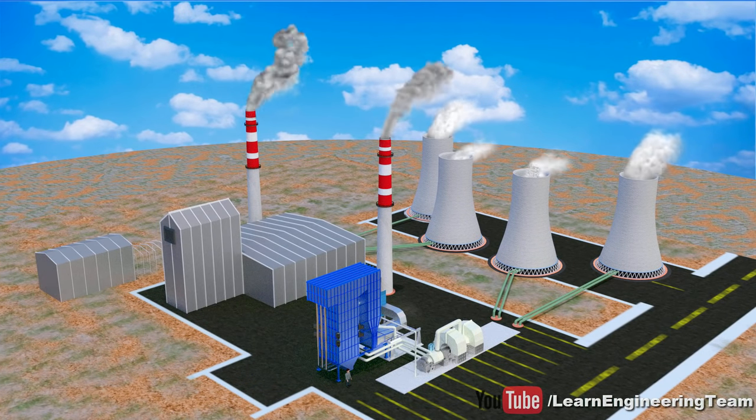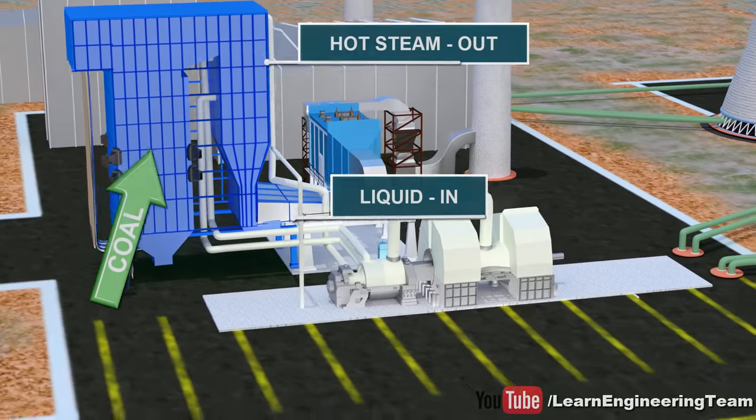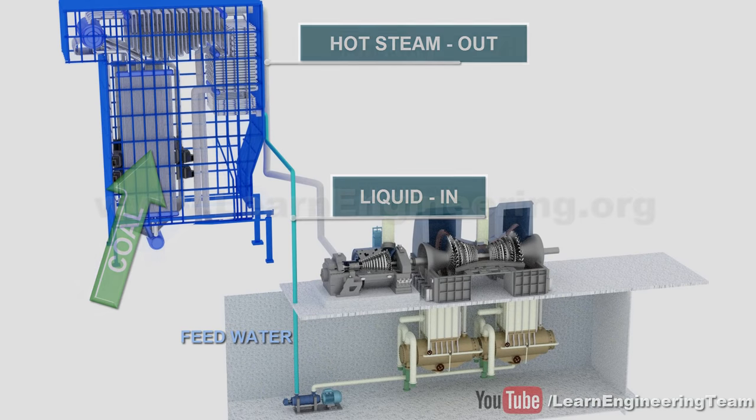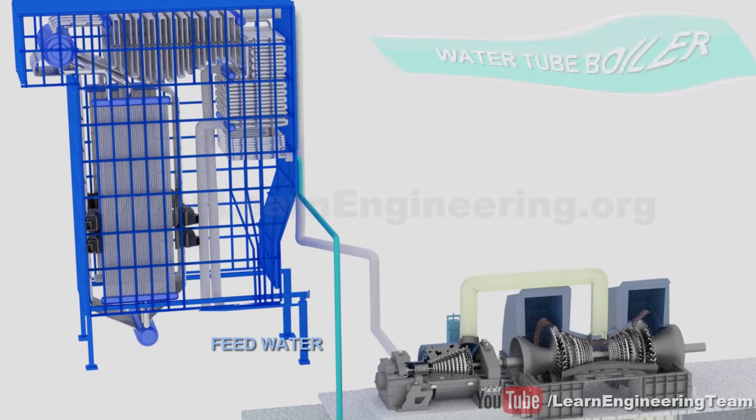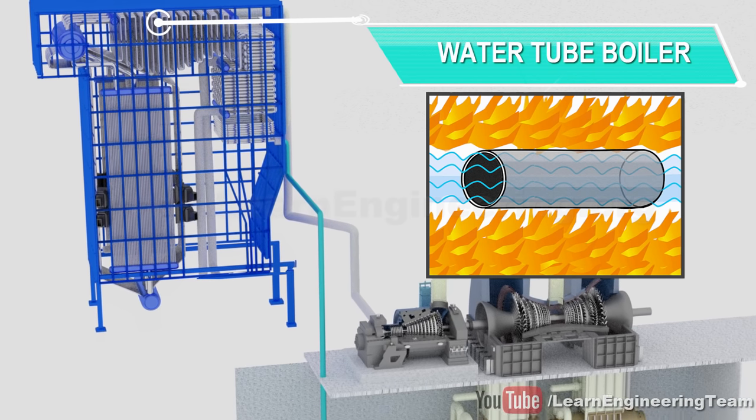The function of the boiler is to convert energy contained in the coal into high temperature steam. Large power plants typically use a type of boiler called a water tube boiler where water flows through the tubes and fire surrounds it. Water tube boilers are ideal for high-pressure applications.